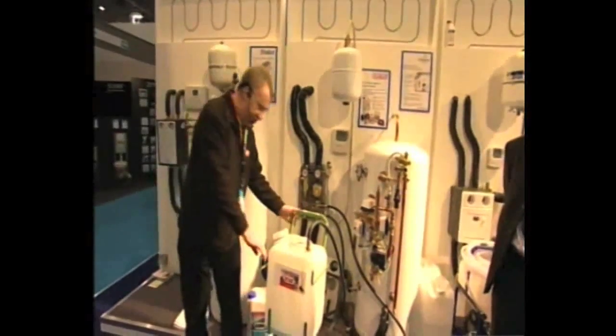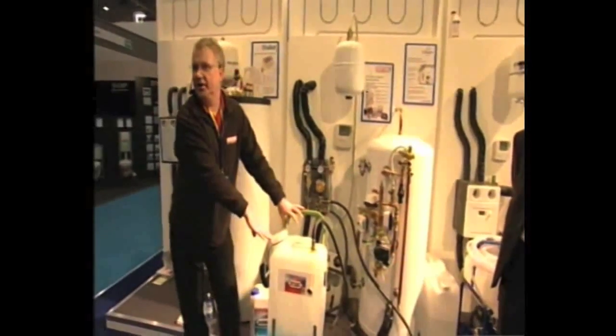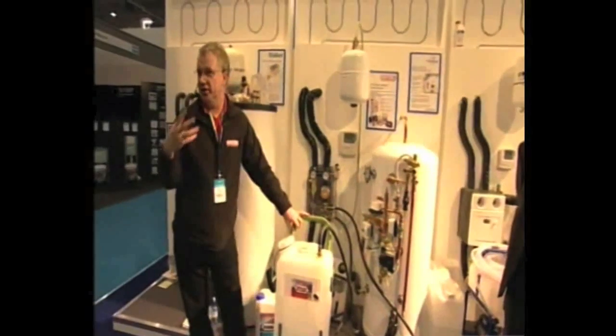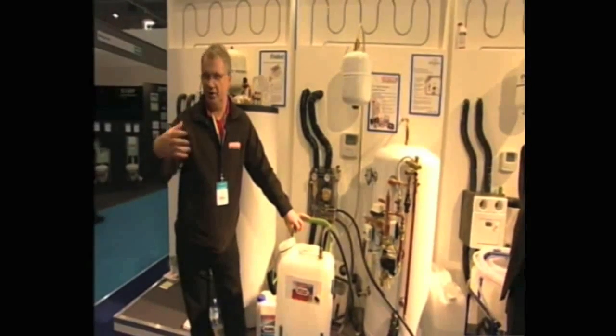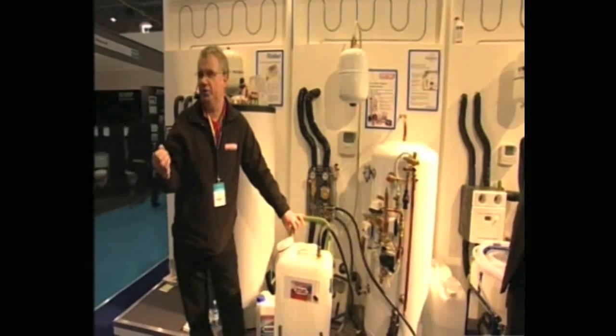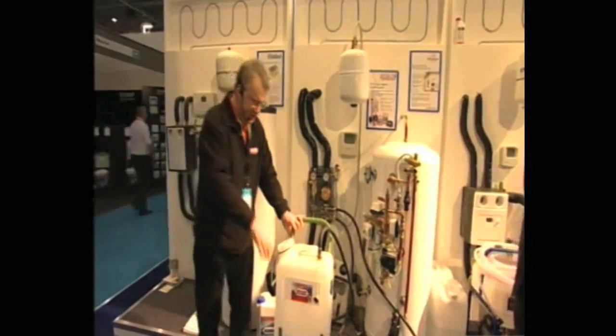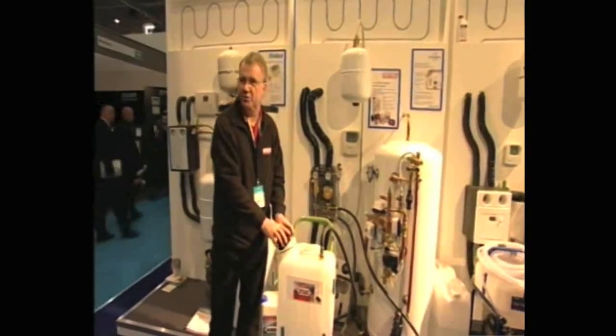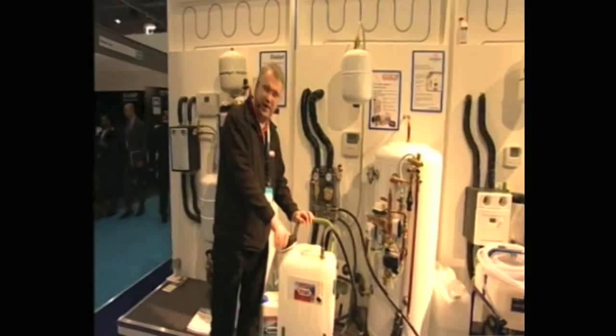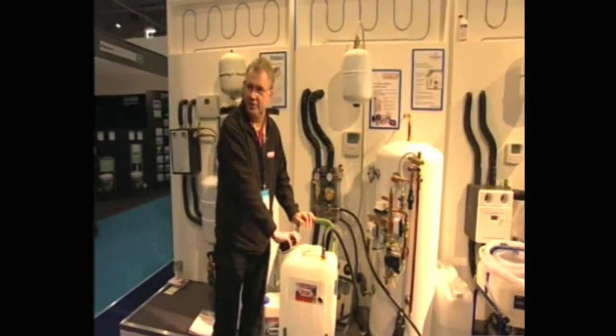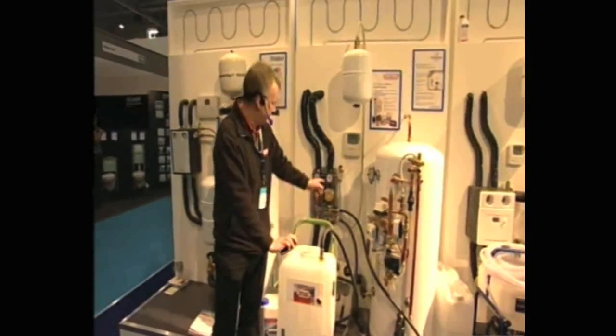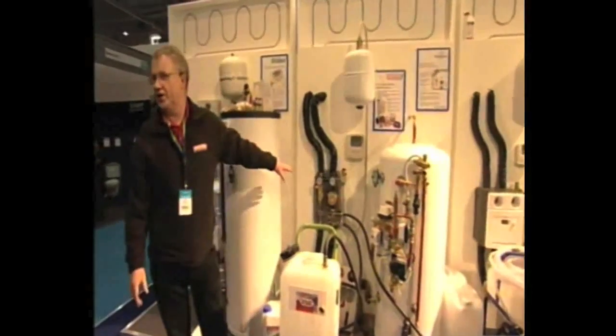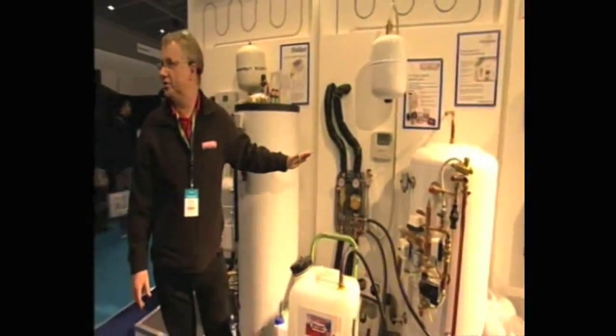Then when you're sure, you will see in here, it will be completely clear. With the glycol, it goes slightly fuzzy with it, slightly misty with the air bubbles. When that's cleared out, it will be completely clear. Then you can replace the top. So this allows you now to pressurize the system by putting this top on, we can then pressurize the system and changing the valve, so we can increase the pressure in the system.